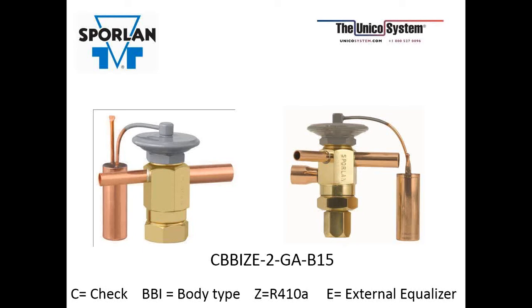Going through the nomenclature, the C in this case means it has a check valve. It has an internal check valve. It will meter in the forward direction, and there's a path through the check valve in reverse flow. It's designed for split system heat pumps. It can be used in air conditioning systems as well, since the check valve just sits idle. The omission of the letter C indicates that it doesn't have the check valve. Next is the BBI. It's the body type. The first B indicates it's a balanced-port version. So it's the balanced-port BI valve.